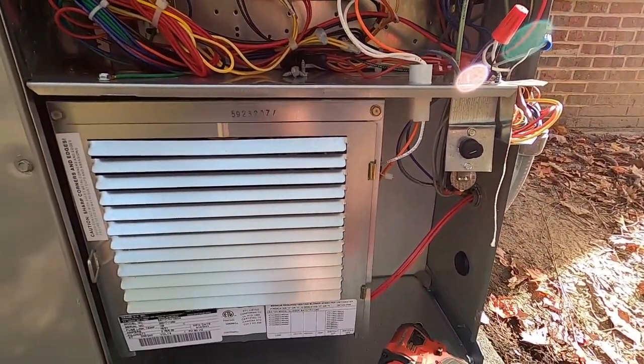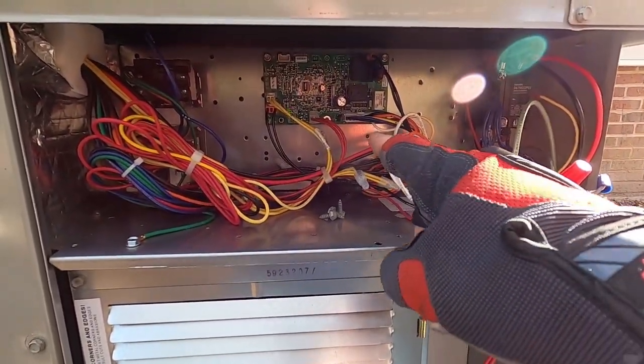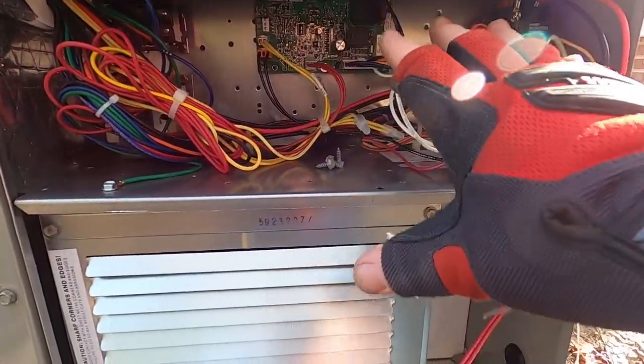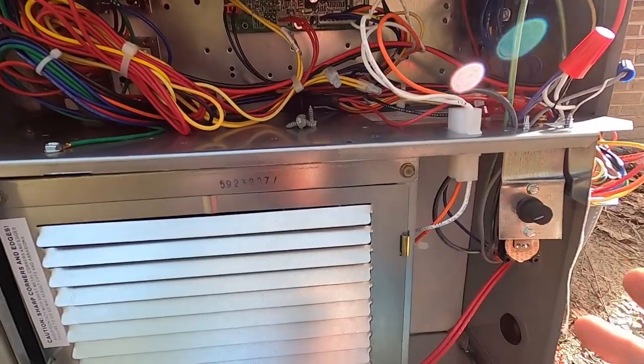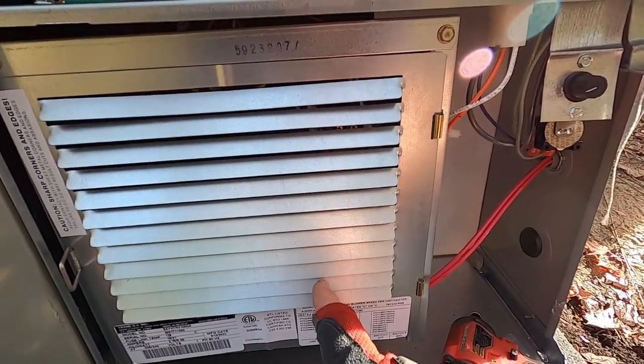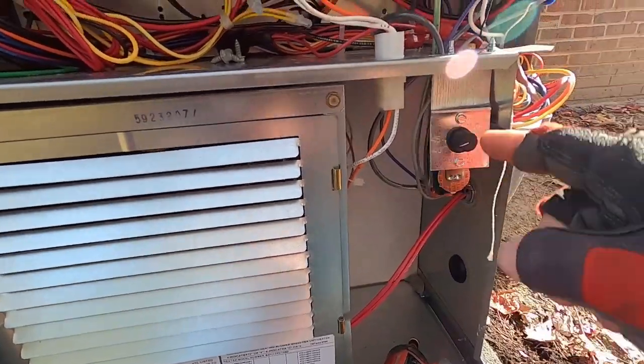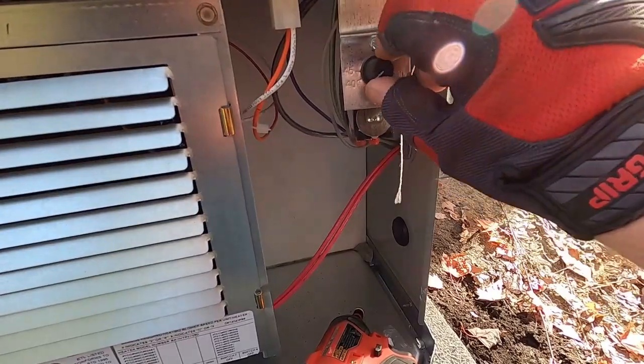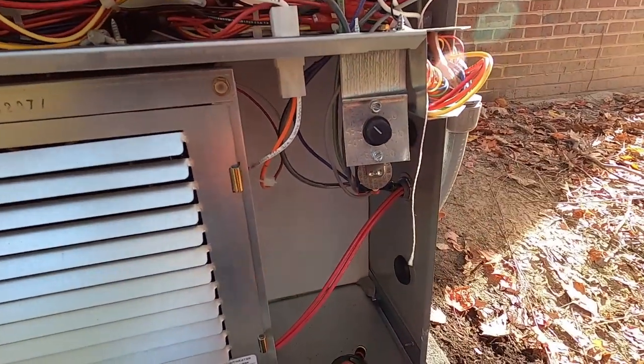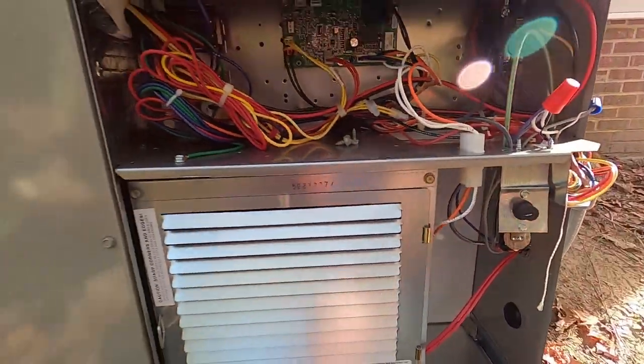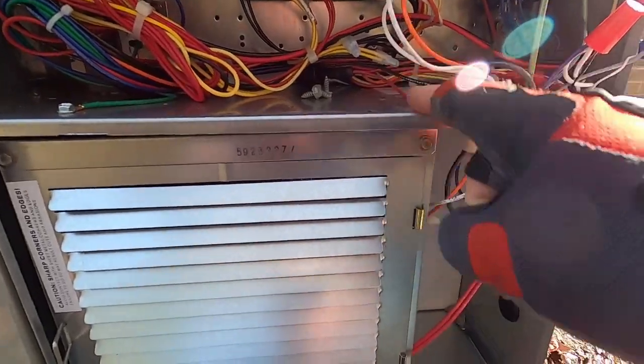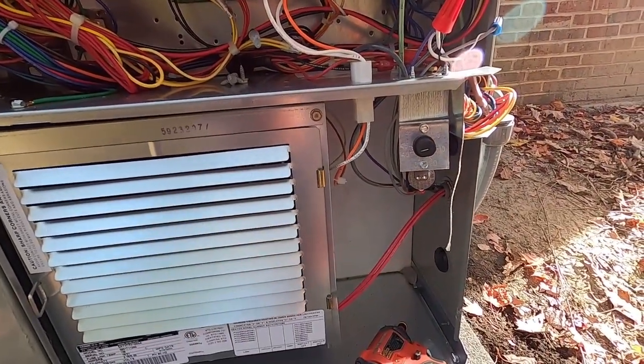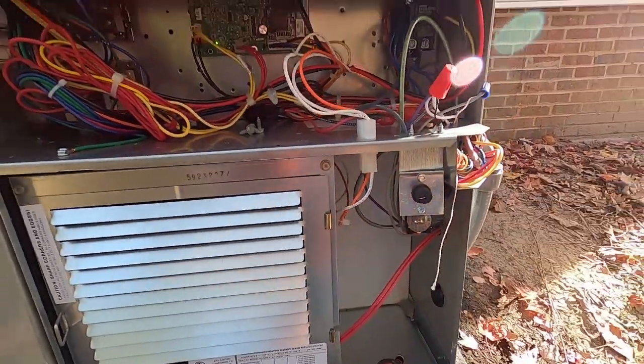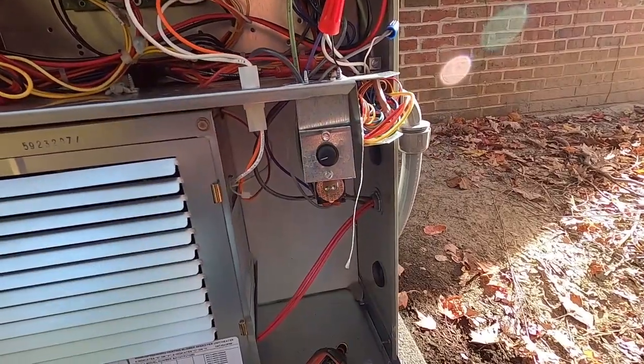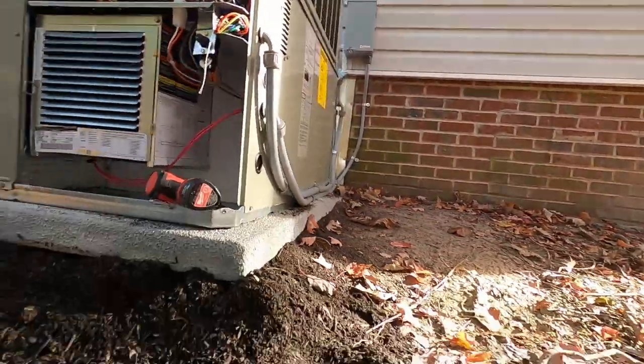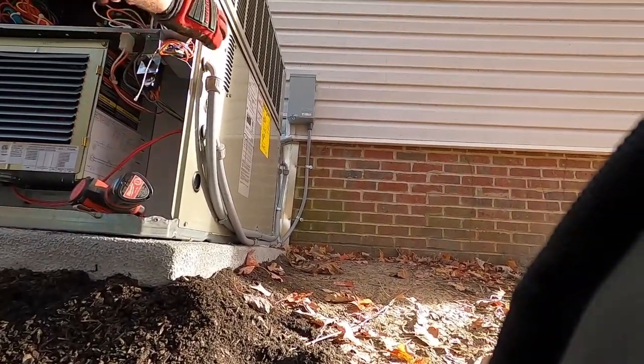But like I said, on a cold night when this thing's running, the back wall of this package unit is the supply side of the air, where a heat exchanger would be in the gas pack, and it stays warm in here. The electronics are in here. The heat strips are right here, but they're not going to come on if the temperature in here doesn't drop below what we're set at here. So I'd have to turn this thing down to, like, I don't know, set it at like 50 degrees really, because I think I had one a couple of years ago. It was 28 degrees outside, and when I set my probe inside this thing, closed it back up, it was still 58 degrees inside of it, 57 inside the electrical compartment. So I'm gonna have to come back and swap that out, but I can still run everything and check it, make sure it's all wired up correctly and working.